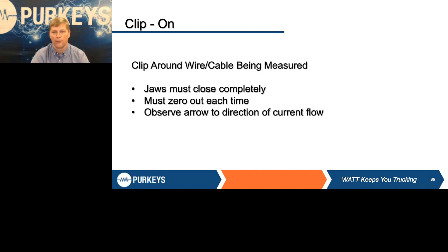A couple other things you got to be careful about too is if you have a positive cable going out, more likely you have a negative cable coming back right next to it. If you were to put that clip on around both cables, what's that going to give you? Basically it'll kind of cancel out the magnetic field, and it'll probably give you close to a 0 reading. So do be careful if you are working with a cable that's mixed in a big harness. Try to pull that one cable away from everything else so you're not picking up the magnetic field from other circuits.